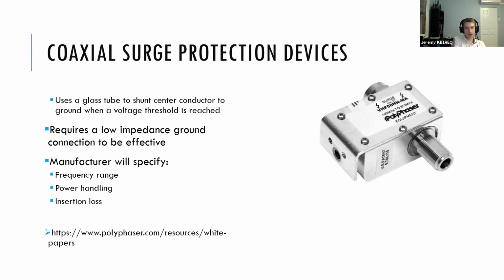So when you're picking a coaxial SPD, and this is obviously one shown here, this is what they look like. They're specified across a frequency range, power handling, and insertion loss, or how much RF signal this will absorb in normal operation. So you just want to be aware when you're buying one that it fits your needs in those categories. It should be pretty clearly stated from the manufacturer what those are.